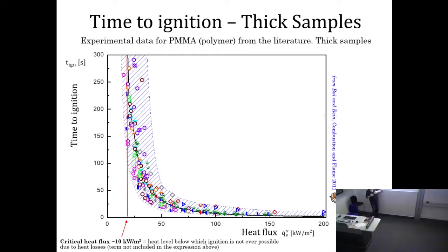But once the fire starts to develop, as ignition has happened, there is a time where the fire has started to develop a smoke layer, and has started to preheat the fuel, particularly the fuel that is next to it. You saw in the sofa, there was initially spread upwards. The heat flux that the element of sofa next to the flame receives is here.